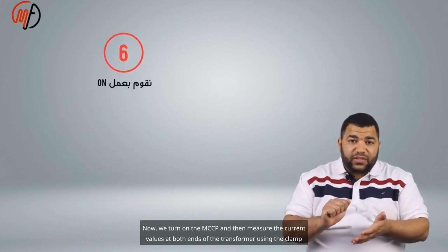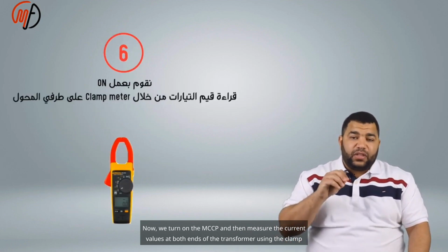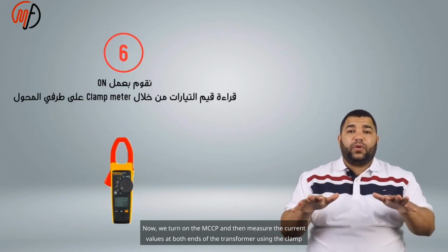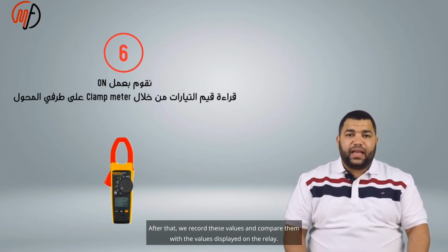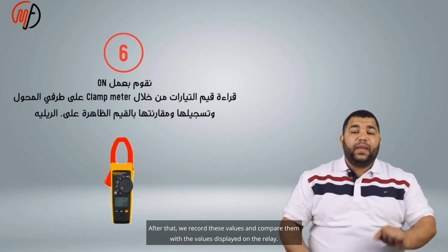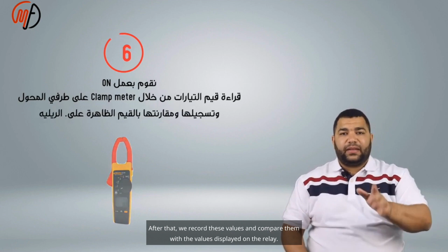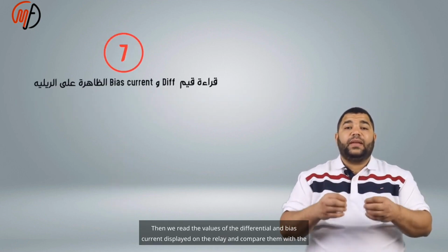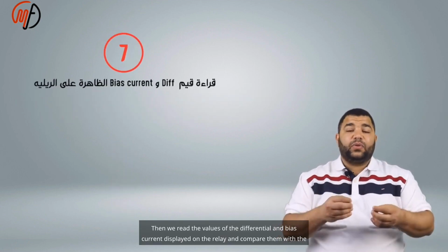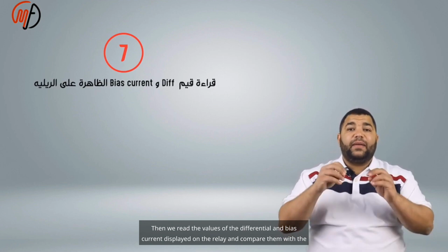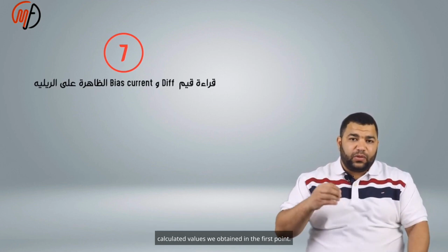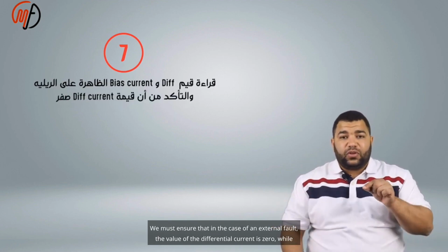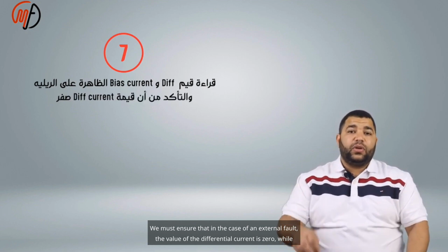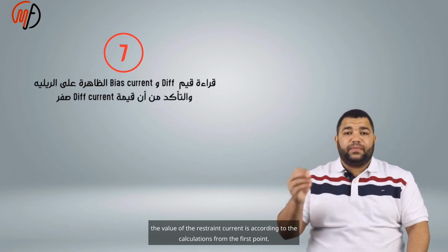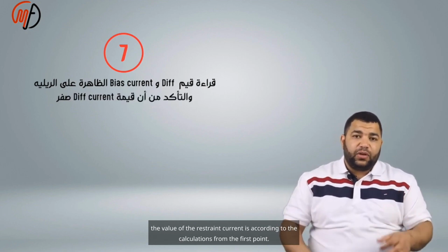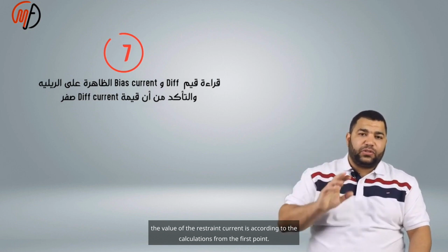Now, we turn on the MCCB and then measure the current values at both ends of the transformer using the clamp meter. After that, we record these values and compare them with the values displayed on the relay. Then we read the values of the differential and bias current displayed on the relay and compare them with the calculated values we obtained in the first point. We must ensure that in the case of an external fault, the value of the differential current is 0, while the value of the restraint current is according to the calculations from the first point.